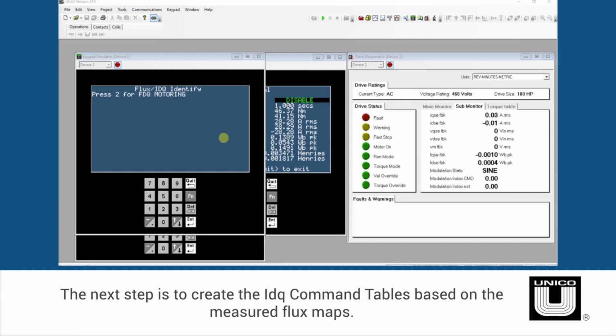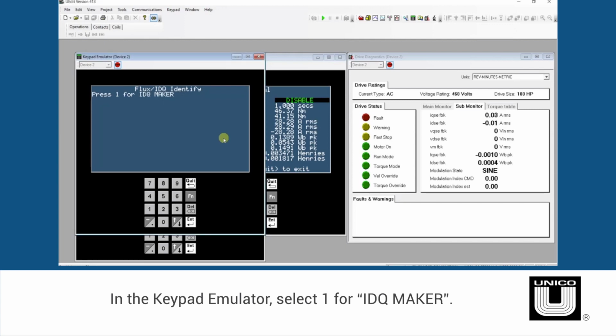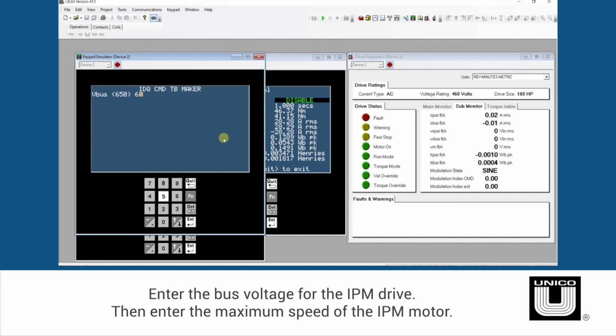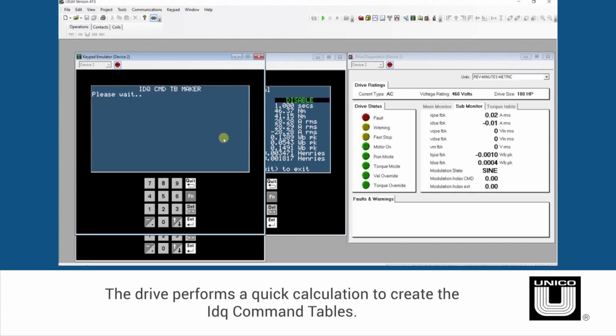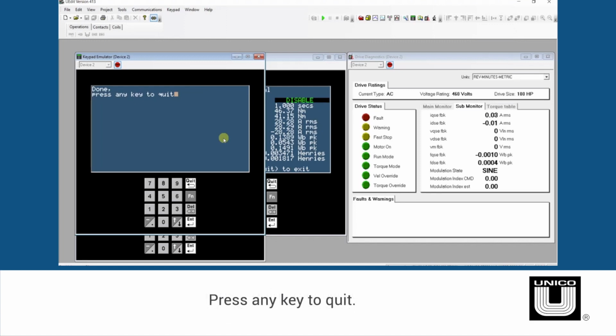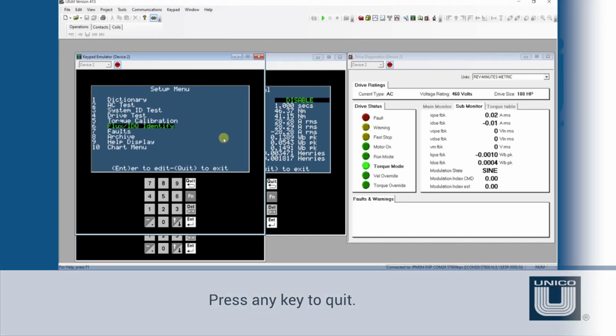The next step is to create the IDQ command tables based on the measured flux maps. In the keypad emulator, select 1 for IDQ Maker. Enter the bus voltage for the IPM drive. Then enter the maximum speed of the IPM motor. The drive performs a quick calculation to create the IDQ command tables. Again, press any key to quit.